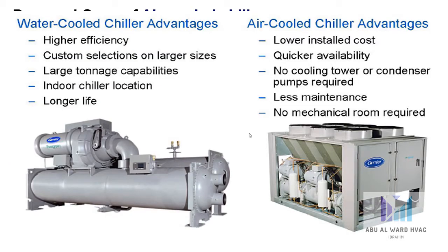Here also we can see some comparison. Water-cooled chiller advantages: high efficiency, custom selection on large sizes, large tonnage capacities, indoor chiller location, longer life. Air-cooled chillers advantages are lower installed cost, quick availability, no cooling tower or condenser pumps required, less maintenance, no mechanical room required.